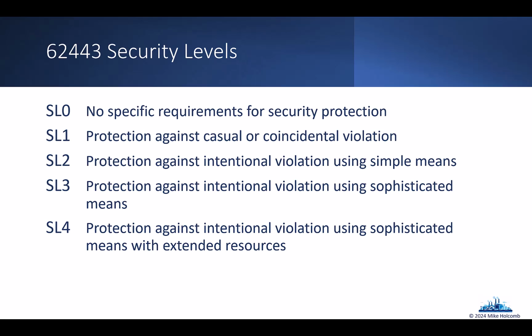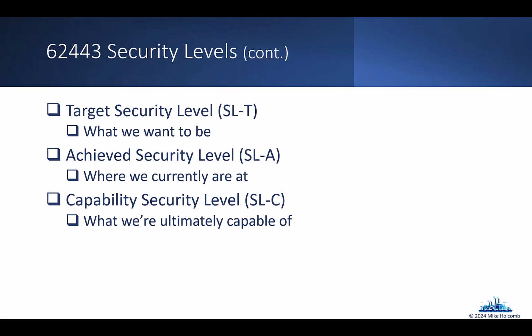So I want at least security level 2 across the board, but there are also some zones where, if I have a SIS, I want to protect that from even the more advanced types of attackers. Again, I'm not going to worry about nation states in most environments, unless I work for some type of government entity or we have something that a nation state has been known to want to steal. I'll kind of leave it at that for the moment. We'll come back and talk a little bit more.